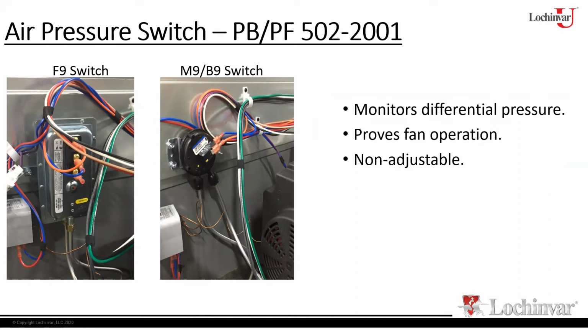But at that point, because of the testing that we did and proved that, yeah, we have to have the block flue switch, we said, all right, we'll just use this differential switch because we already had it in stock. During the development of this product, this is what we had available. So we said, we'll just use this switch and make it consistent across the board. That's why you see this low air switch, if you will, on the M9, B9, 500 through 2 million models, even though I don't need the low air function, I just need the block flue function. It was just for expediency and consistency for us.